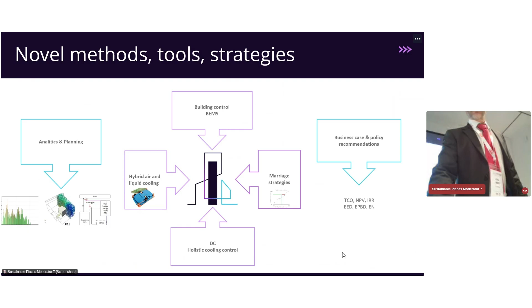For analytics, we developed an analytical method to estimate the heat potential, or waste heat absorption potential, of a building, and what potential it has to store energy and its flexibility. Then we add a metering strategy - where to meter, what to measure. It matters where to measure. One key finding is to measure not too many places, but enough places. What matters isn't the mains temperature, but the system - your HVAC or heating - and connecting where temperatures are lower, since the mains is always the highest temperature.